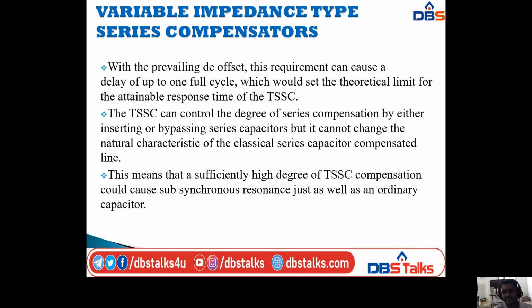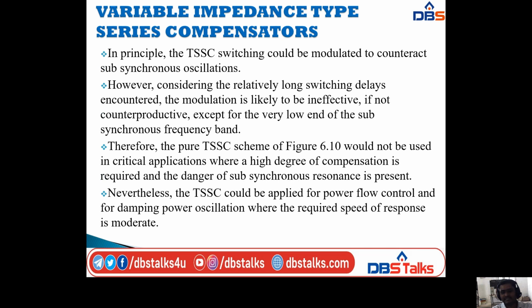This means that a sufficiently high degree of TSSC compensation could cause subsynchronous resonance just as well as an ordinary capacitor. In principle, the TSSC switching could be modulated to counteract the subsynchronous oscillations.